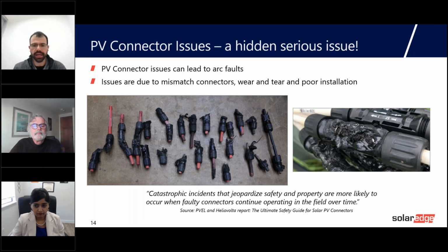And what is Sense Connect? First, before I explain the feature and the benefit, let's take a look at an industry problem that we're seeing: issues with PV connectors. I was reading that PVEL and also HelioVolta came up with a report specifically on this issue of mismatched connectors, wear and tear, and poor installation of connectors. In other words, over time the connectors are not properly connected, and because of wear and tear you start to have issues in the connector, leading to catastrophic failures.